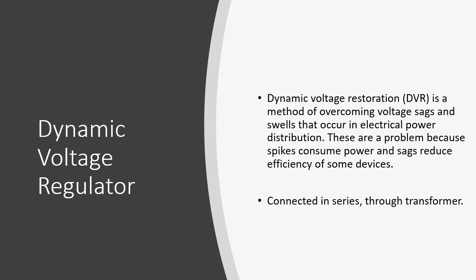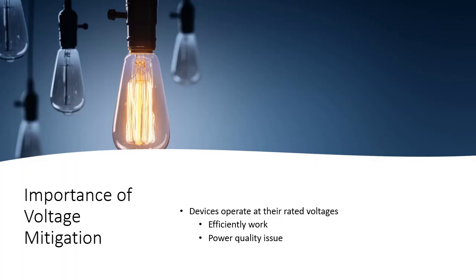We have different techniques to restore voltages. One technique is the Dynamic Voltage Restorer, or DVR. Another technique involves FACTS devices — Flexible AC Transmission Systems. DVR is a method of overcoming voltage sags and swells that occur in electrical power distribution systems. These problems matter because voltage spikes and drops consume power and reduce the efficiency of devices. A DVR is always connected in series through a transformer.